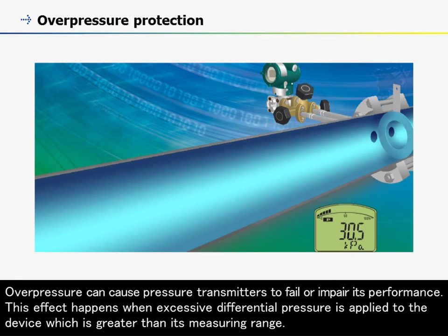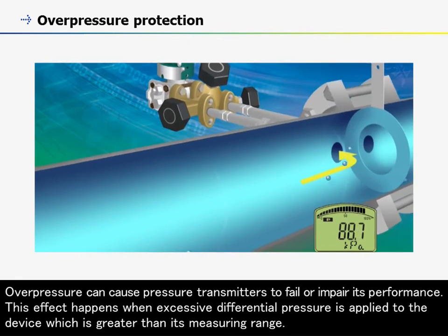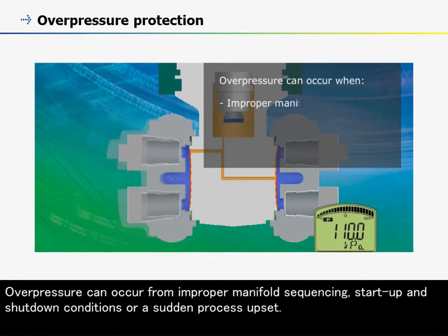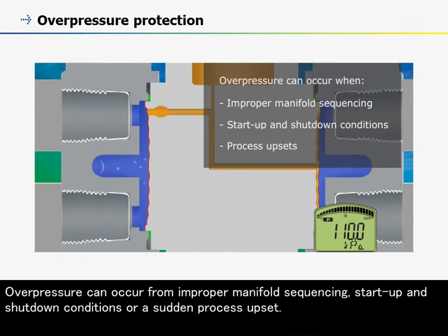Here is a demonstration of how overpressure occurs and how it is prevented with Yokogawa products. Overpressure can cause a pressure transmitter to fail or impair its performance. This effect happens when excessive differential pressure is applied to the device, which is greater than its measuring range. Overpressure can occur from improper manifold sequencing, start-up and shutdown conditions, or a sudden process upset.